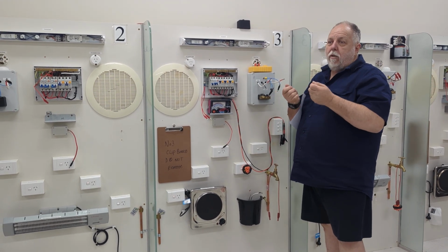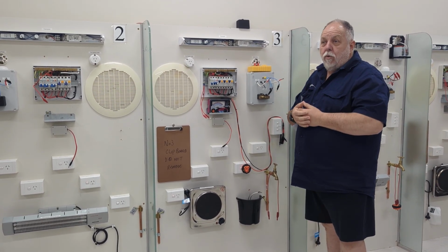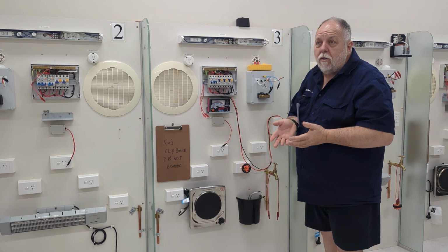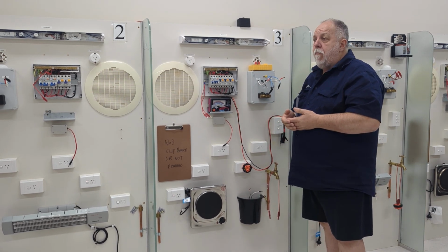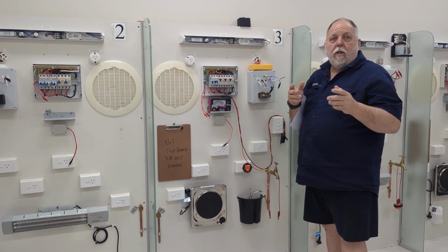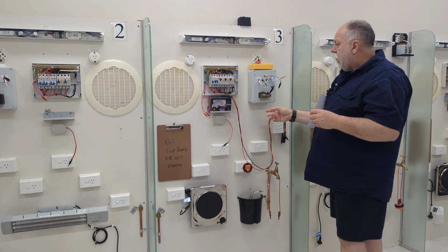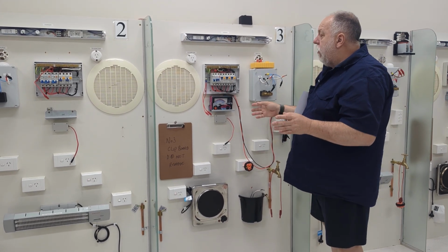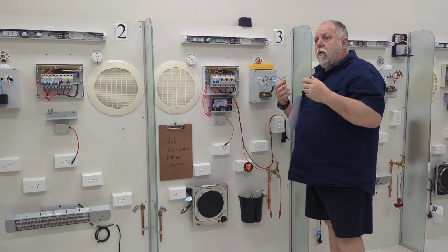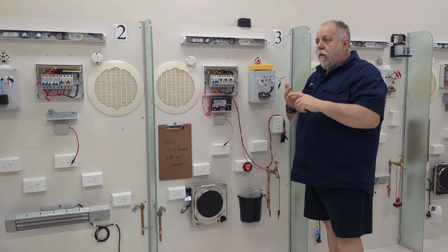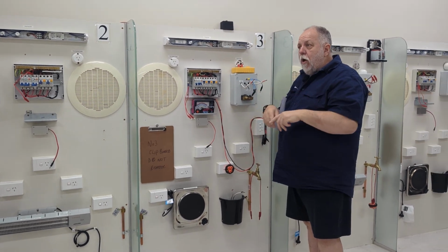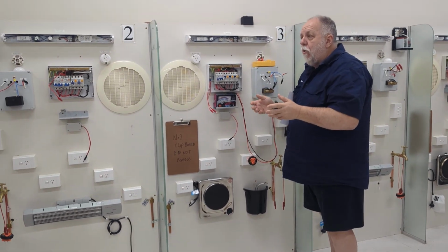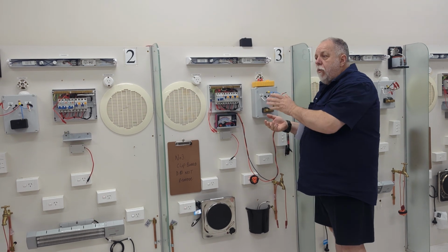All right, unless you break the twin active and do an insulation test between the two conductors, that's the only time you might pick it up. All right, so you've got to be careful when you're doing tests like that. Okay, the first test we're going to do when you look at 8.2 is you have your earthing. So when you look at the flow diagram, that's what I'm telling you to look at. If you're not sure, pull your reg book open and that'll give you a start.